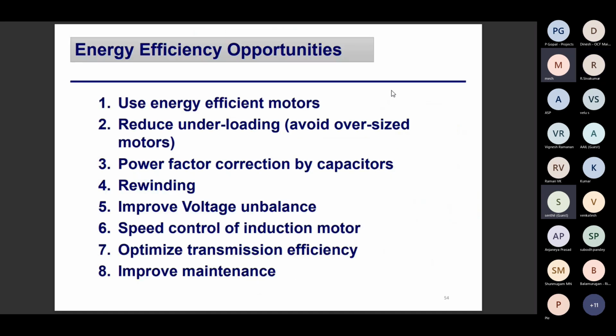Next one. These are the various options for energy efficiency opportunities: use energy efficient motors, reduce underloading, avoid oversized motors, and power factor correction by capacitor. Motors of more than 25 HP can be fitted with capacitors, whenever the starter is started, with star to delta conversion. Small capacitors can be installed based on calculations, so that the voltage rating is also improved. Also avoid rewinding too many times and improve voltage unbalance. For speed control of induction motors, VFDs can be adopted wherever possible. Optimize the transmission efficiency, and improve maintenance activity. These are the various energy efficiency opportunities. Next.